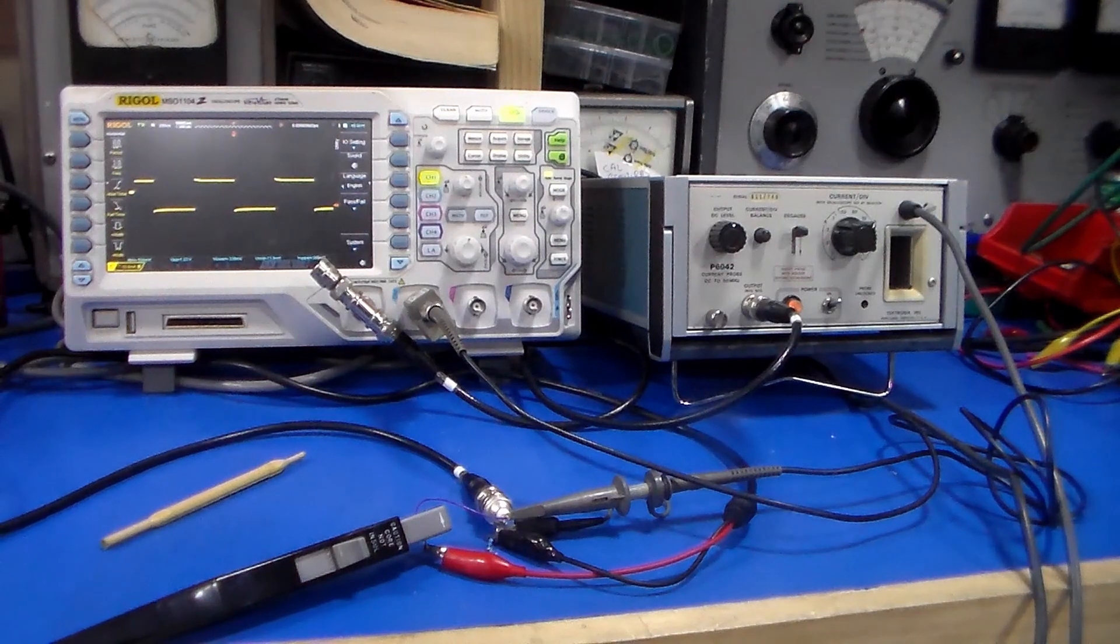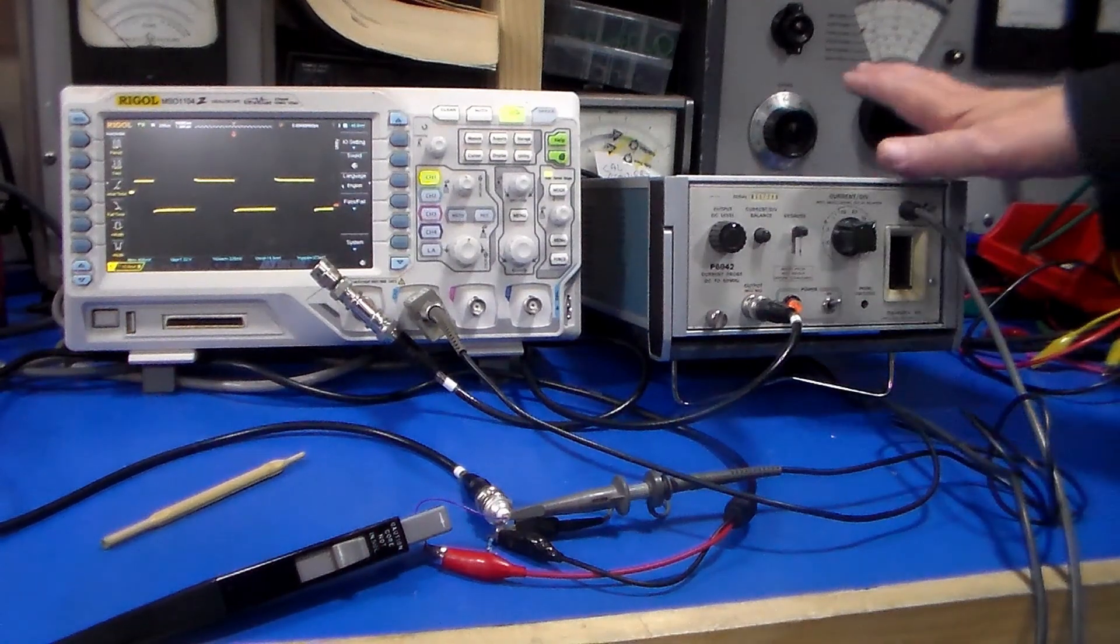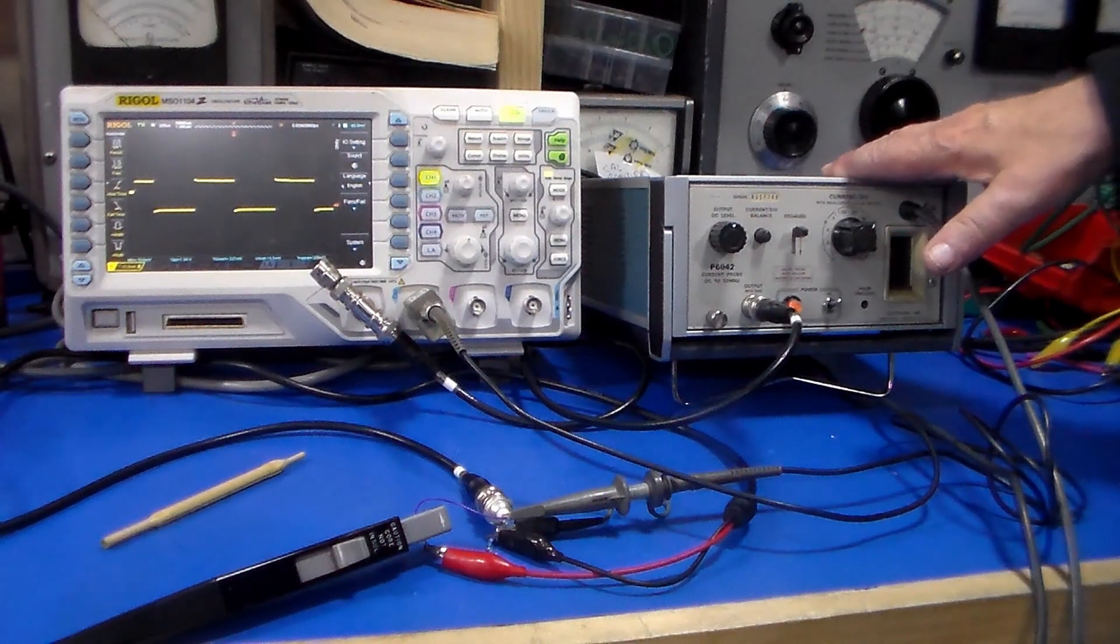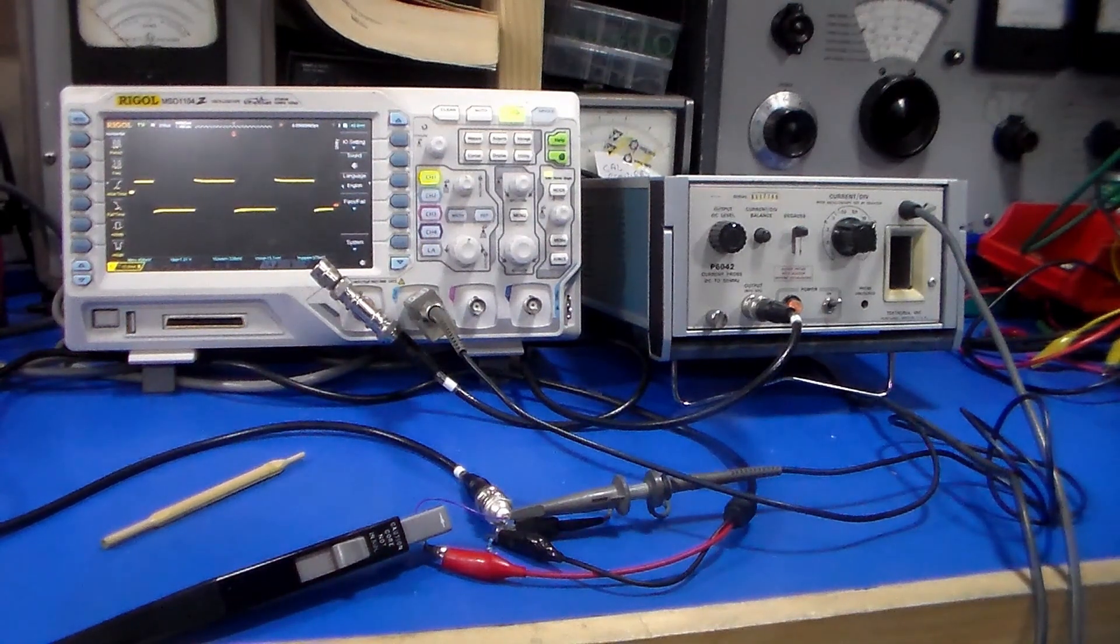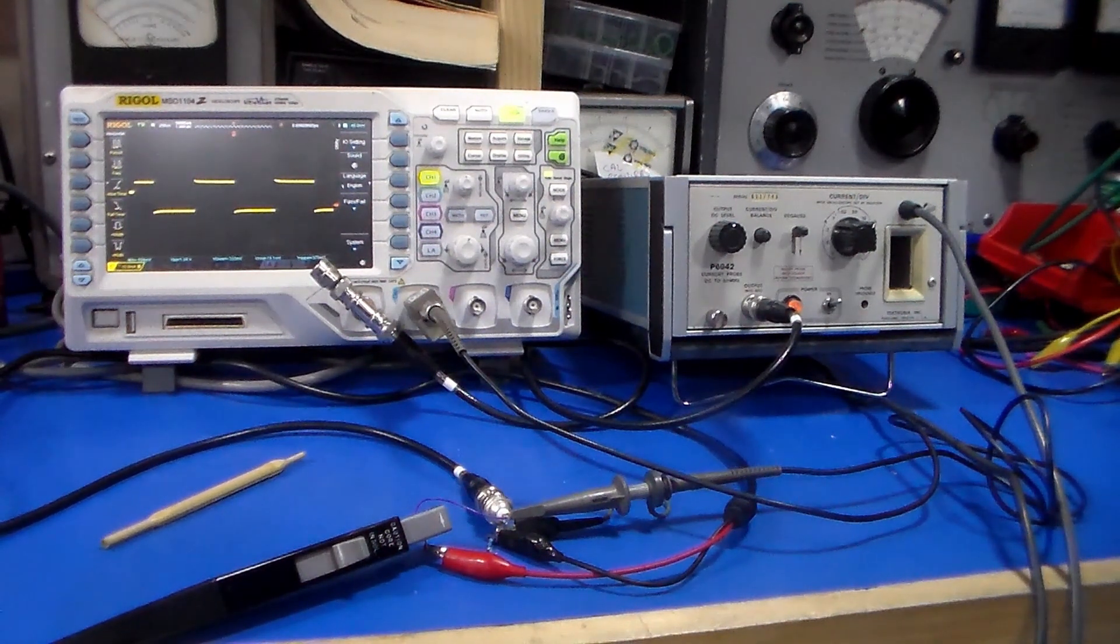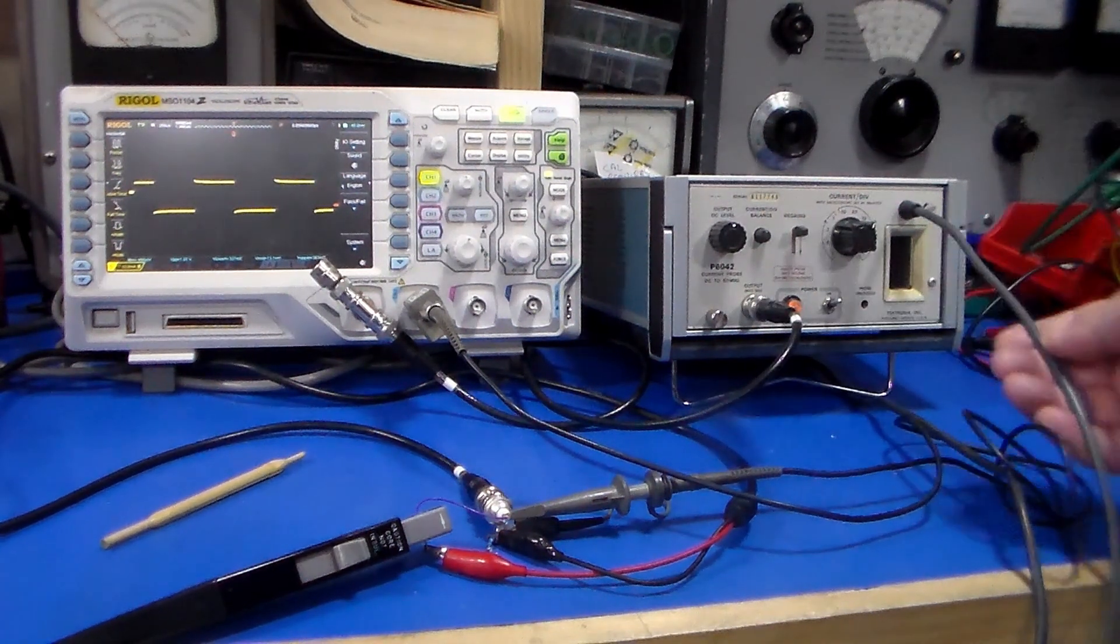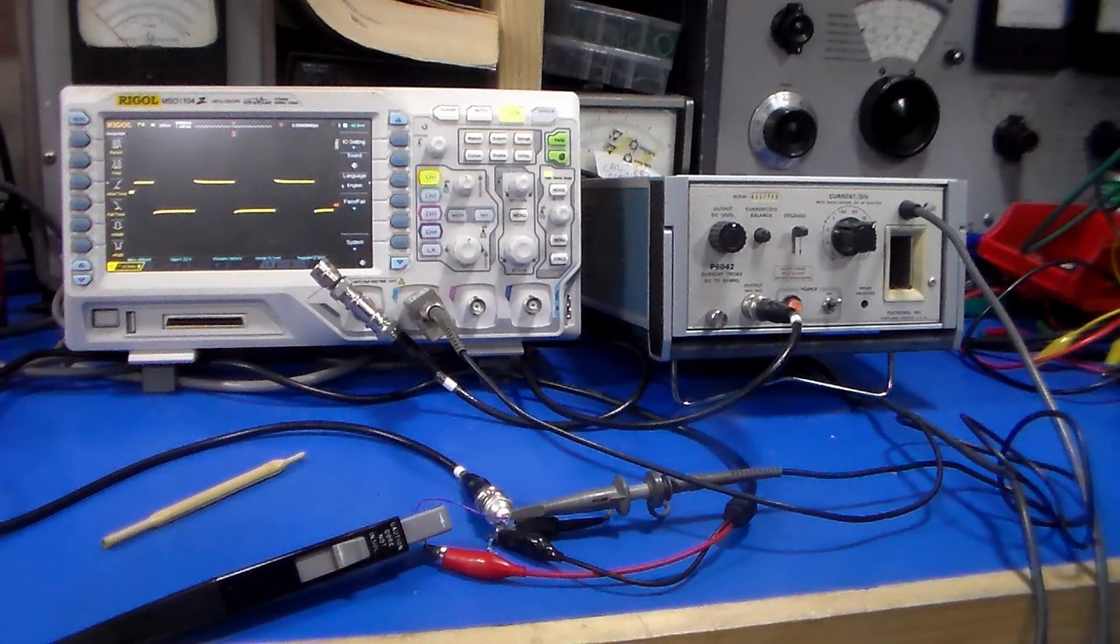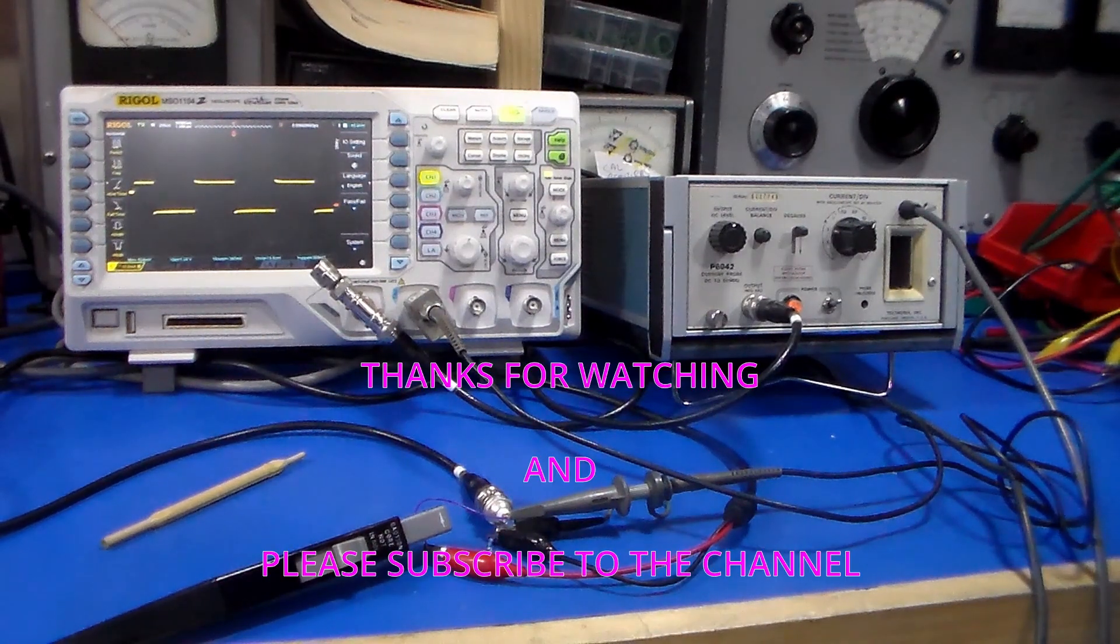Really the point of this whole video is not so much about the probe itself. I mean I have shown you a little bit of the internals and whatever, but the main point of the video is: whenever you're diagnosing a fault, don't ever jump to conclusions, particularly if you've already had a failure and the evidence sort of points toward the same failure having occurred, which in this case was the cable. But what you should do is always go back and do all your fundamental checks first, because it can save you a lot of time.